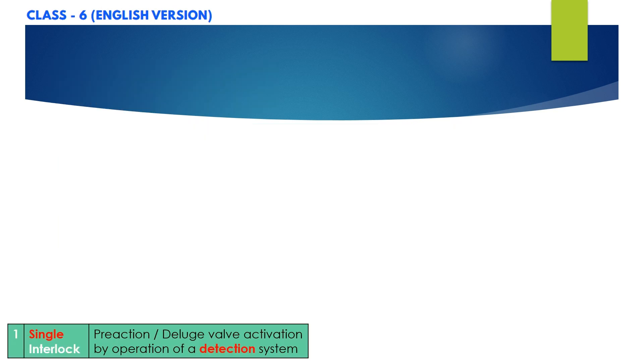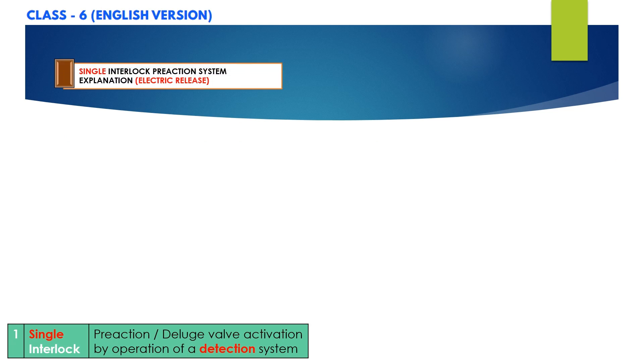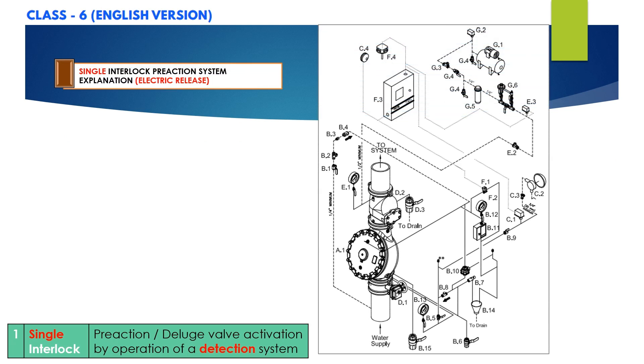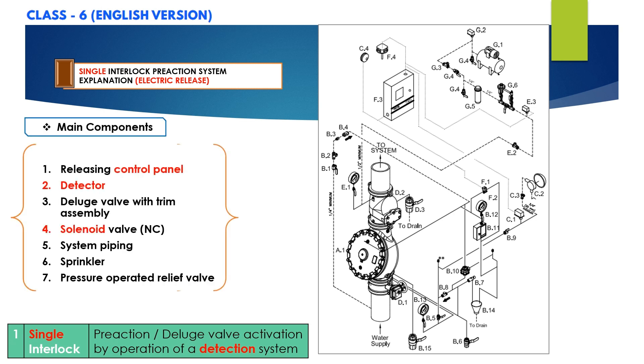Let's look at the single interlock pre-action system with electric release. The schematic shown on your screen is an electrically controlled single interlock pre-action system. The main components for this type are: releasing control panel, detector, deluge valve with complete trim assembly, solenoid valve which is normally closed, system piping connected to the sprinklers, and pressure operated relief valve.